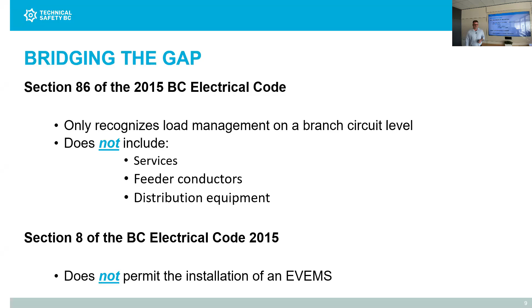So next, let's take a look at the information bulletin itself and some of the prime pieces of information we want to take from it. The whole purpose of this information bulletin is to bridge the gap, because in the 2015 BC Electrical Code, Section 86 only recognizes load management on a branch circuit level. It does not include load management on services, feeder conductors, or distribution. In addition, the 2015 BC Electrical Code Section 8 does not permit the installation of any sort of EVEMS systems at this time.